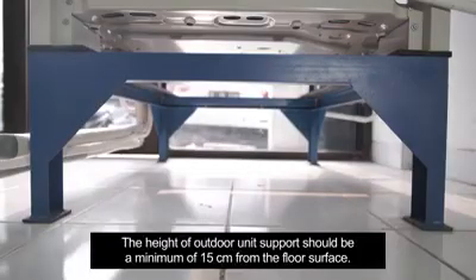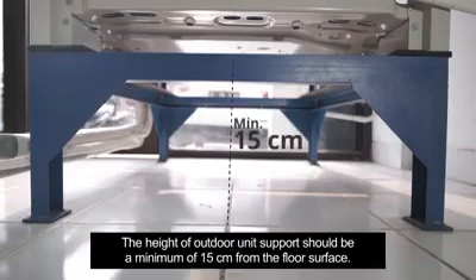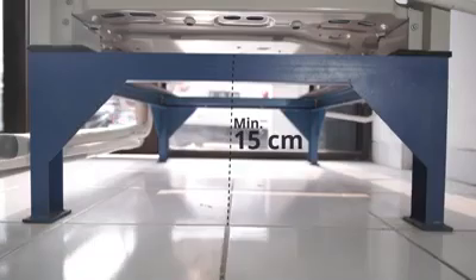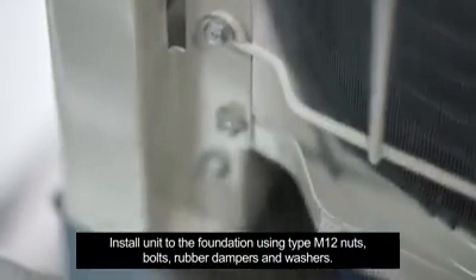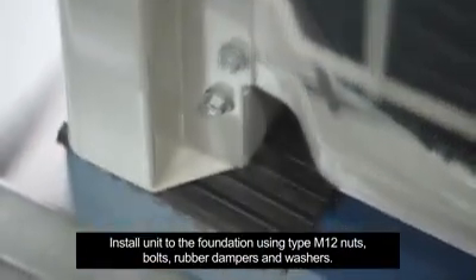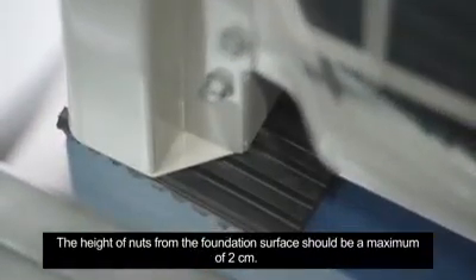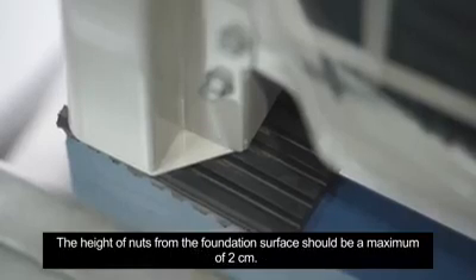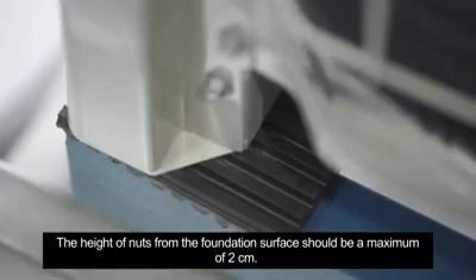The height of outdoor unit support should be a minimum of 15 cm from the floor surface. Install unit to the foundation using Type M12 nuts, bolts, rubber dampers and washers. The height of nuts from the foundation surface should be a maximum of 2 cm.